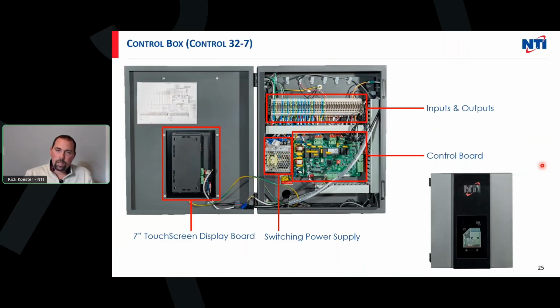Control box, exactly what it sounds like. You've got the touchscreen there, and a touchscreen display board on the back of it. There is a switching power supply here on the bottom left, the control PCB, and then up here is where we would have all of our inputs and outputs. There are some pigtails off here. Those are all around sensor locations, and they're all nicely labeled. You'll see that all the ends of the sensors themselves, and even some of the extension cables, have a specific label for the sensor, making it a lot easier come install to make sure we're plugging in the right stuff. Mistakes do happen, we get that, but it's easy to identify once you go through it. And we'll go through the labels on the power, inputs and outputs shortly.